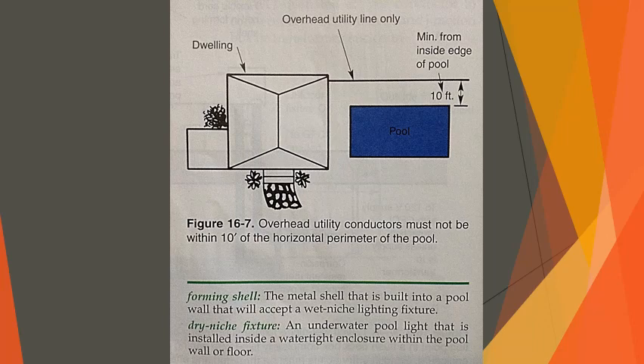Overhead conductor clearance. It should be emphasized that conductors should not be run above a swimming pool. However, for utility company wiring, there are some exceptions worth noting. Keep in mind that these exceptions are only for service lines such as telephones, television, or power cables provided by the utility. Further, even within the allowable exception criteria, the conductors must not pass directly over the pool or within 10 foot horizontally from the inside edge of the pool. Figure 16-7 shows what is permitted according to section 680.8 and table 680.8 of the NEC.